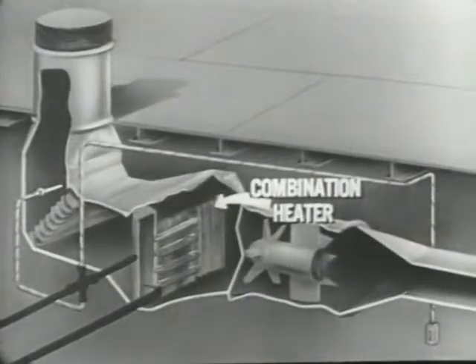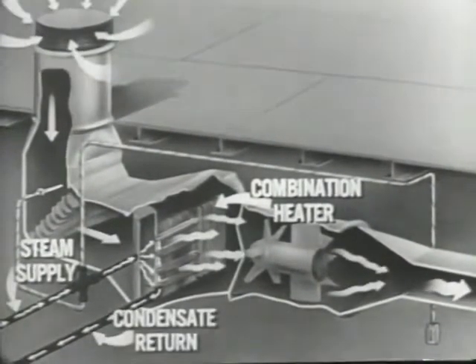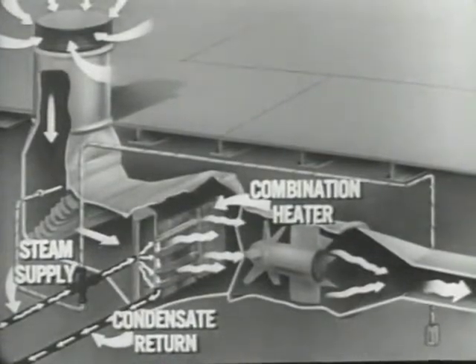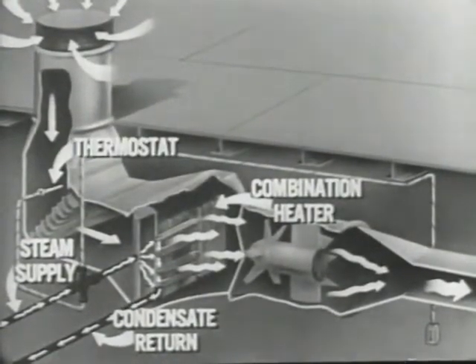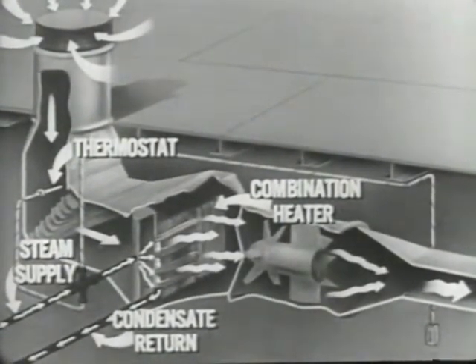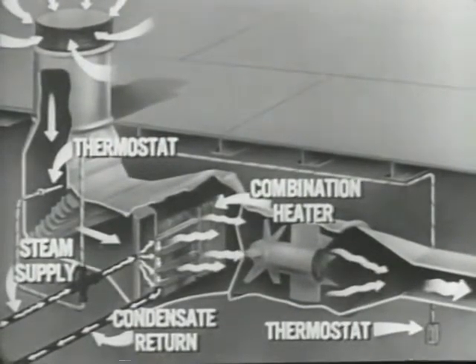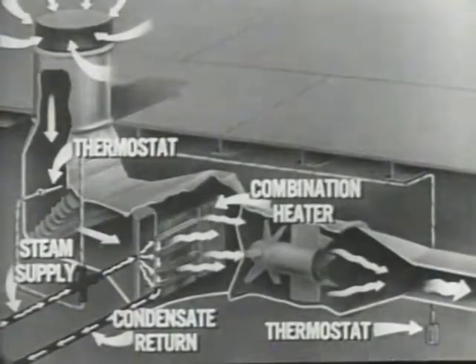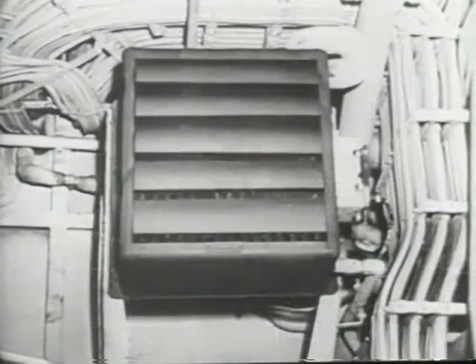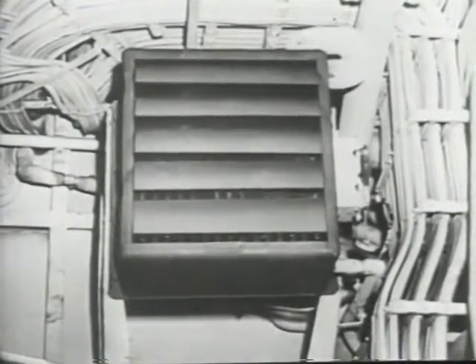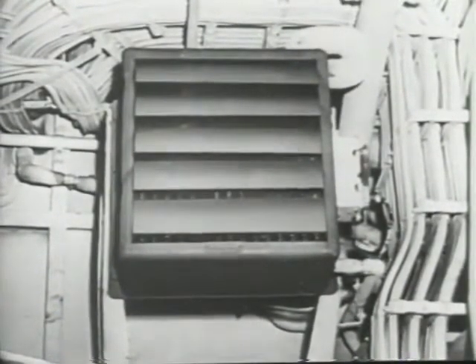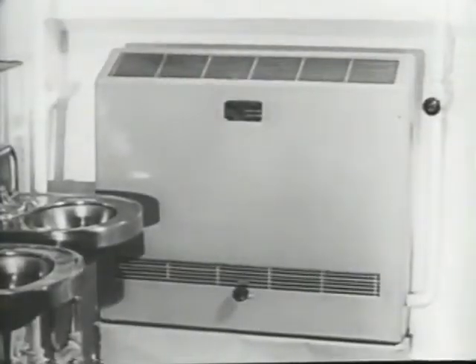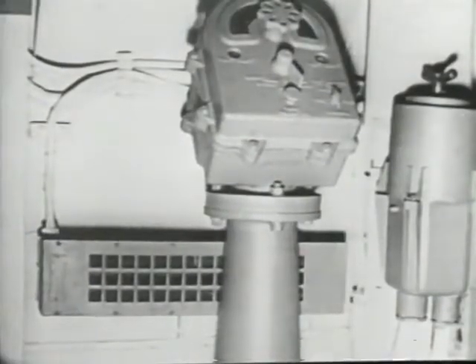In some installations, a combination heater serves as both a preheater and a reheater. In this case, the steam valve is controlled by a thermostatic bulb located on the inlet side and by a thermostat located in the compartment which is heated. Where it is not practical or desirable to provide heated air through the ventilation system, unit, convection, or electric heaters provide the space heating.